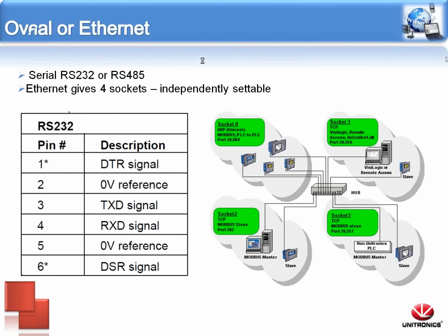You can see in these graphics here, it's just a pinout of the RS-232. This is the port on the controller. RS-232 is typically just 4 wires. You have a transmit and a receive, and also just 2 grounds is all that's being used. The inside 4 pins on the side of your PLC.